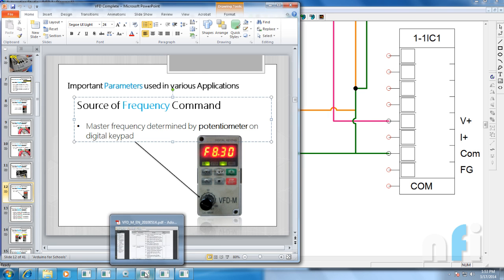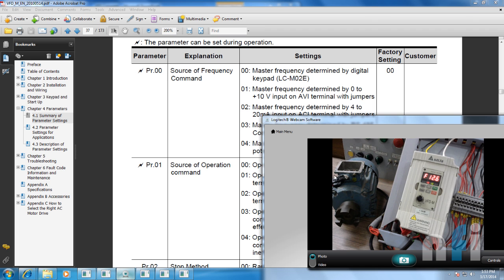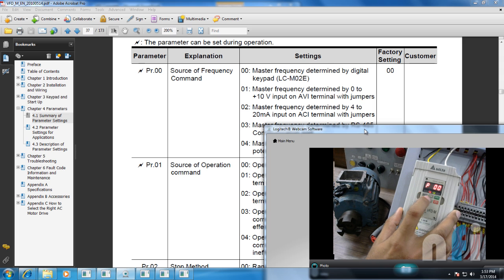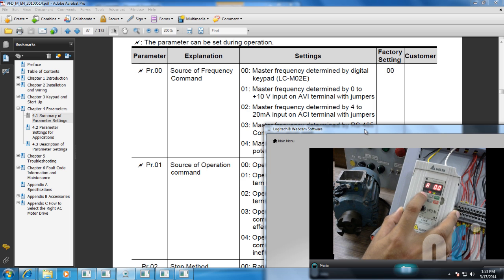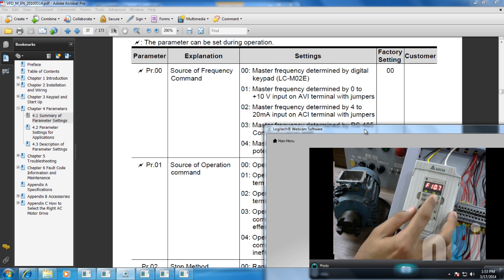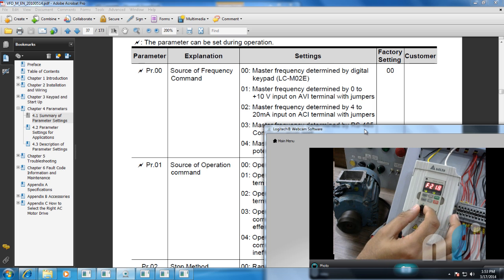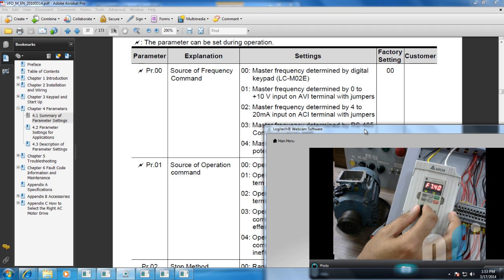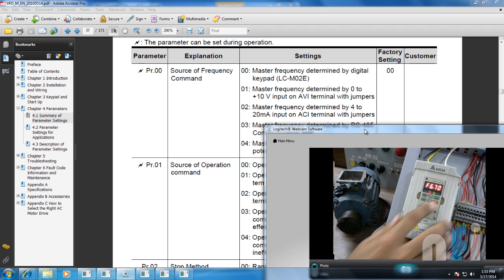The last parameter says master frequency determined by a potentiometer on the keypad. For that we change parameter 00 to value 04. Going into the drive: mode, parameter 00, press enter, put 4, press enter again. Now when I go back, this frequency can be changed by this potentiometer — frequency can be increased or decreased. It's no longer taking frequency from the card or the buttons, just from this potentiometer.